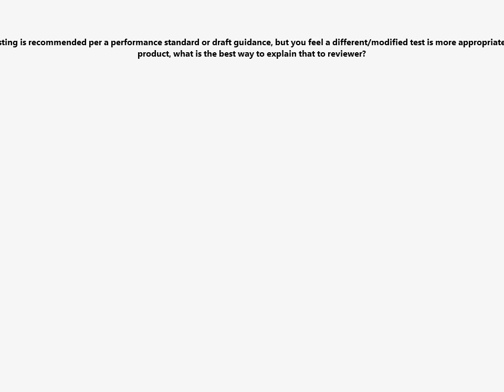The next question asks, when testing is recommended per a performance standard or draft guidance, but you feel a different or modified test is more appropriate for your product, what is the best way to explain that to the reviewer? Up front. That's why I say an overall test summary is a great way to do that. You say, hey, this guidance or this standard required 10 tests. We did all 10 of them. We did something different for test 9, and here's why, and here's why it's justified.